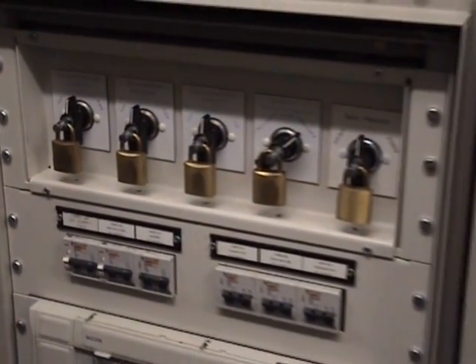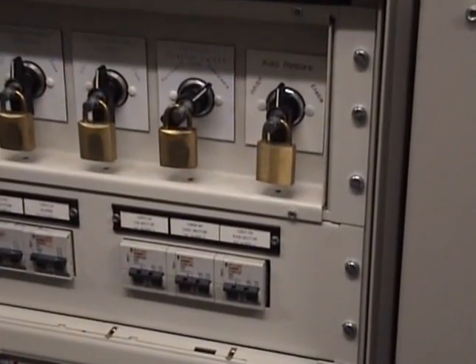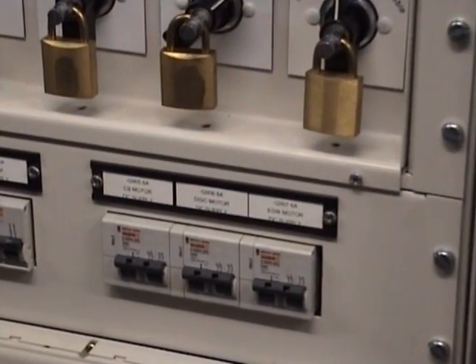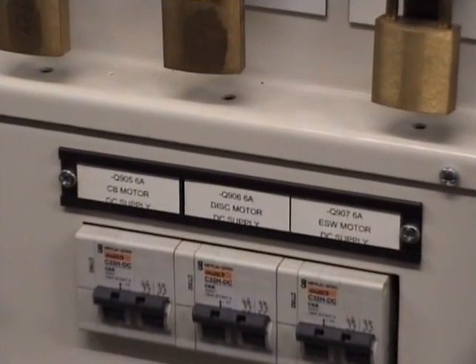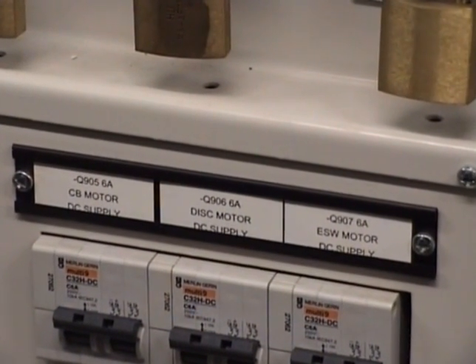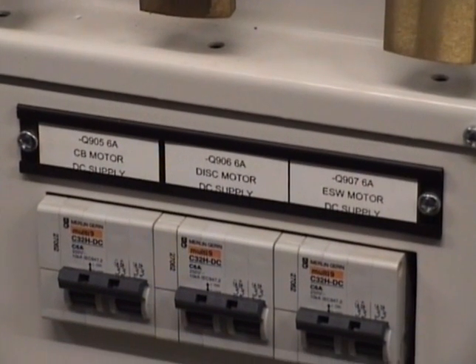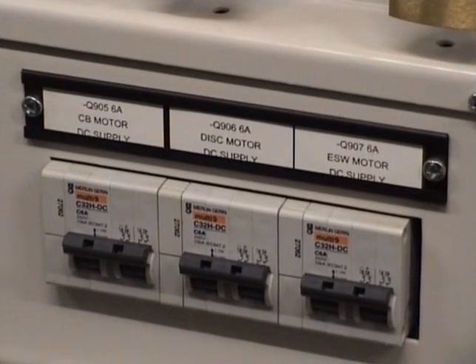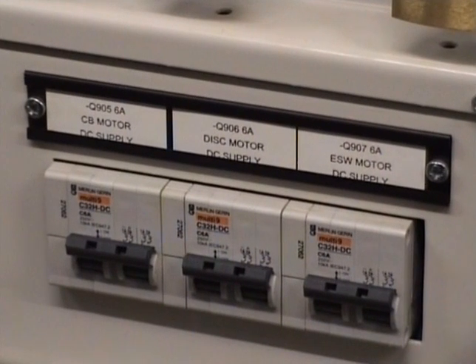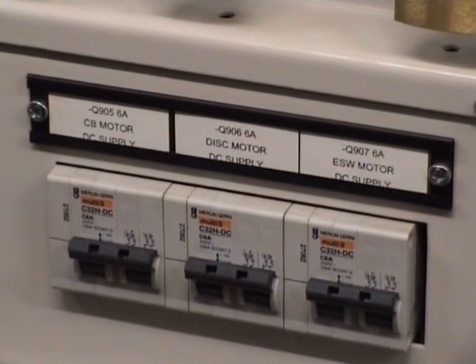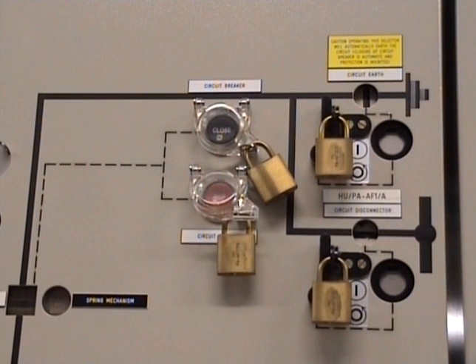Below this are some MCBs. The right hand ones control the supply to the circuit breaker motor, the disconnector motor and the earth switch motor. In the event of isolation, these are used to isolate the supply to prevent inadvertent operations. In the centre of the picture, the black and red buttons are a mechanical operation for closing and tripping the circuit breaker. Under isolation conditions, they are usually padlocked, so they cannot be operated.